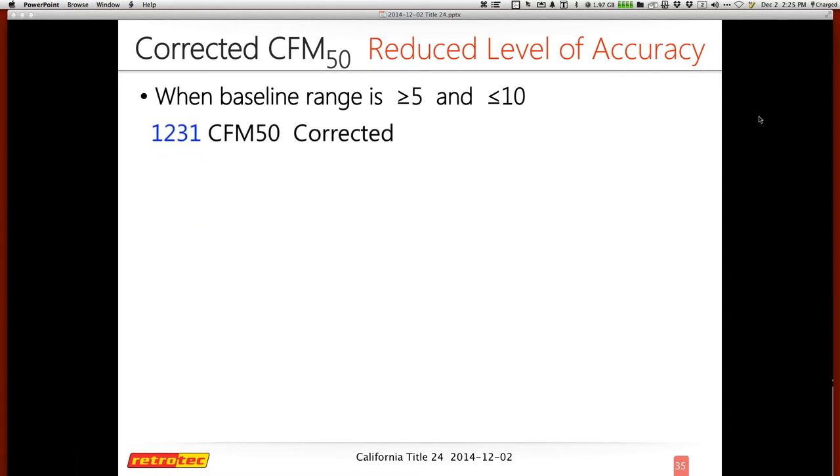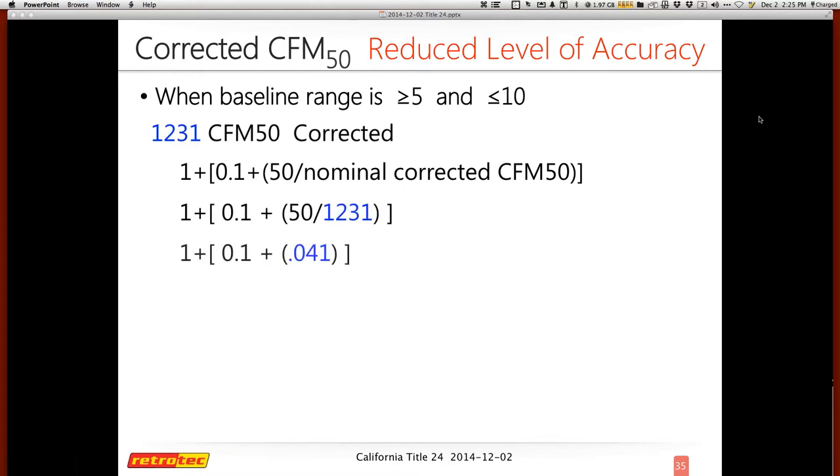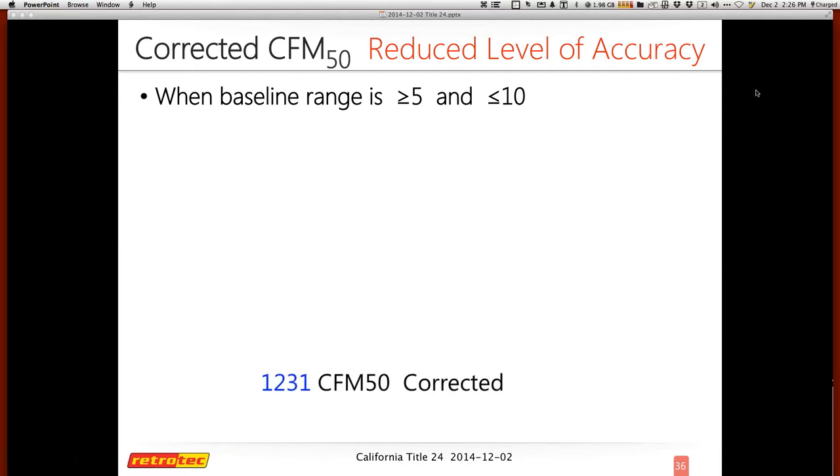If it's a windy day and your baselines fell between five and less than ten — the reduced level of accuracy — you need an additional correction. The formula is: multiply your corrected altitude and temperature CFM by a factor of (1 + [0.1 + 50 / your corrected CFM50]), resulting in a correction factor of 1.141. That gives a final CFM50 of 1,405. It's not as complicated as many people make it — it's mostly about determining what level of accuracy you're at and being honest about it.